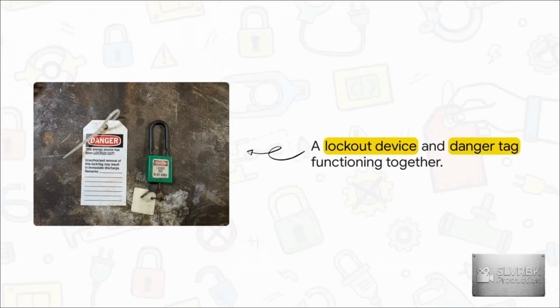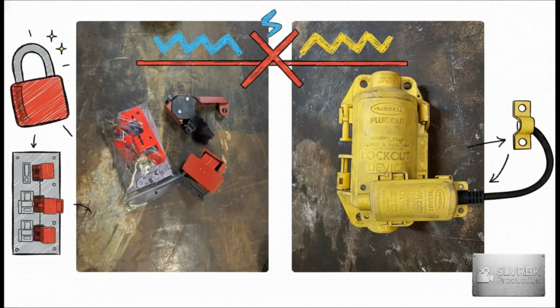physical lock. Now, what's really interesting about this setup is how the physical lock acts as a positive restraint, while the tag serves as a mandatory, prominent warning against unauthorized removal. Together, they are a real game changer for safety. OSHA basically says that if an energy isolating device is capable of being locked out, you must use a lock. This means if it has a hasp, a built-in lock, or can be blocked with things like circuit breaker blocks or cord end isolation devices without permanent alteration, you have to lock it out.